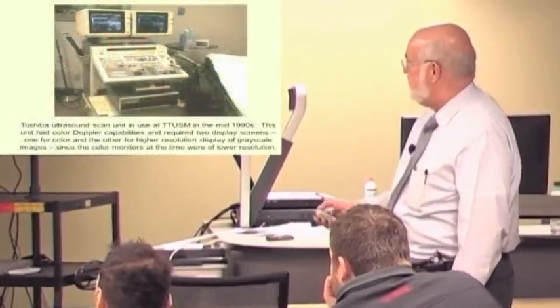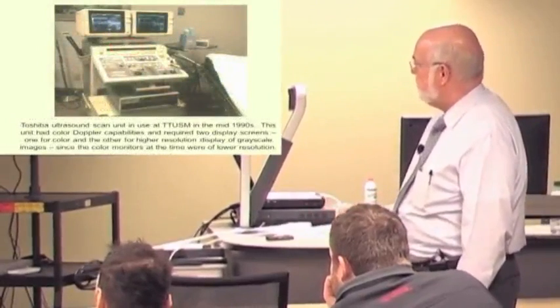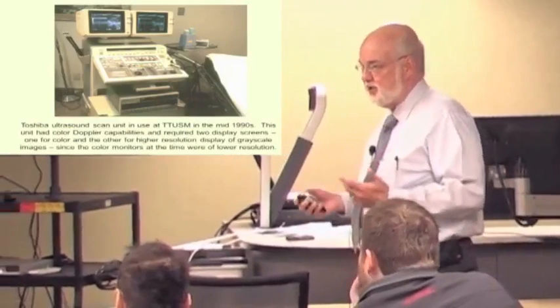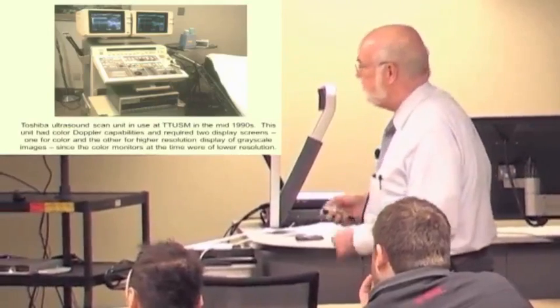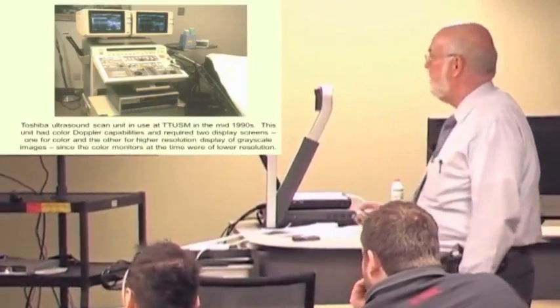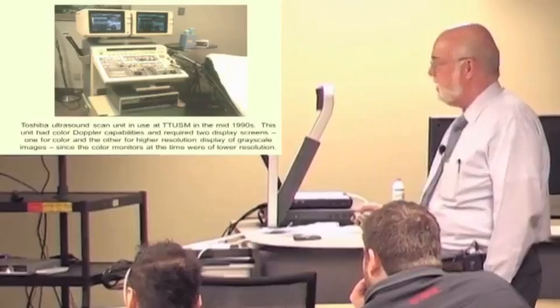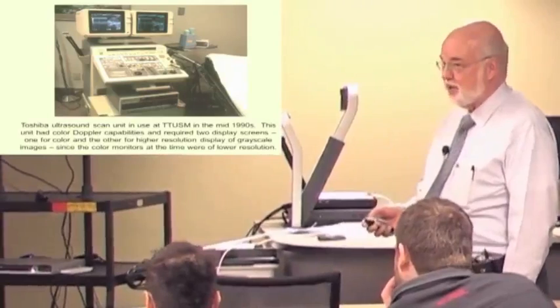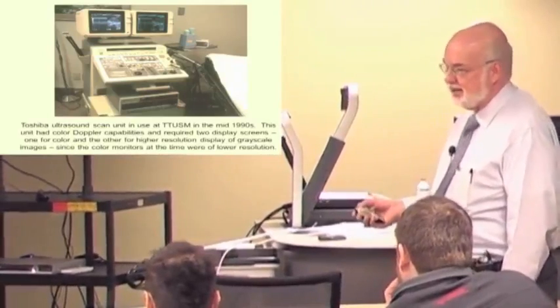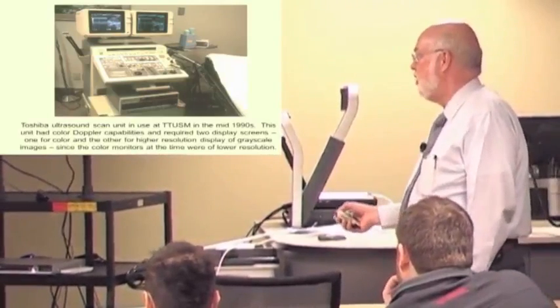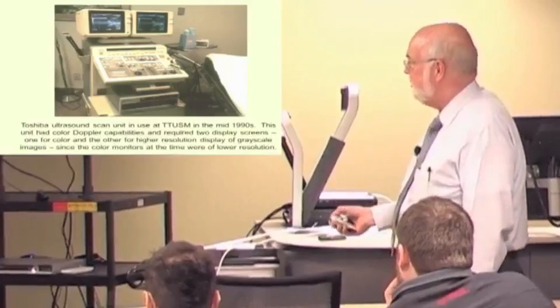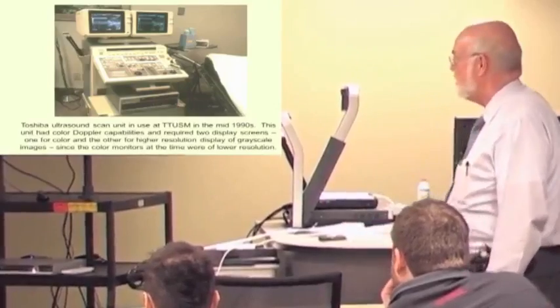By the mid-1990s, we had this unit, which was from Toshiba. But the thing to notice is it has two monitors on it. By this time, we have real-time moving pictures. And we'll talk about how you do that when we get to transducers in a minute. But it had to have the two monitors because by now we were doing color Doppler. The color monitors at the time were not high enough resolution to display the grayscale images. So you actually had to have one monitor for gray information and one for color information. And this thing obviously is the size of a good-sized washing machine.